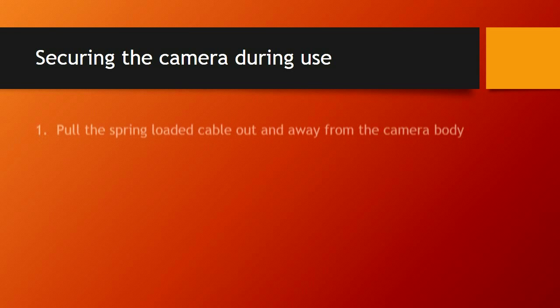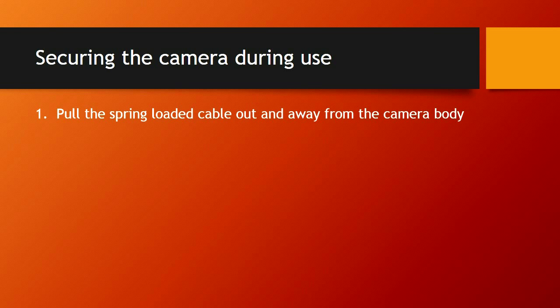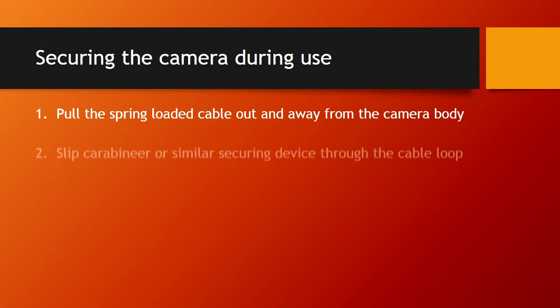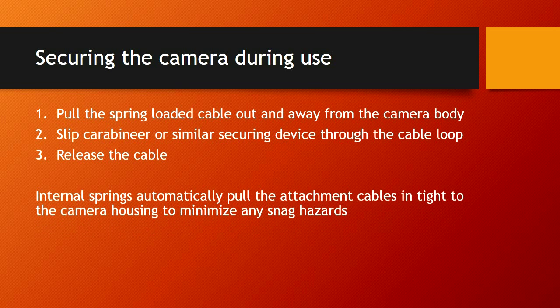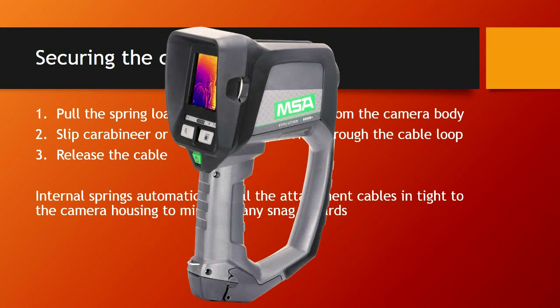Securing the camera during use: pull the spring-loaded cable out away from the camera body — there are 3 of these, one at the base of the camera and one on each side of the display screen. Pull it out, slide the carabiner through, latch it on, and release the cable. The internal springs automatically pull the attachment cables in tight to the camera housing to minimize snags. We recommend hooking to the cable attachments on the side of the screen to carry the camera in a different position and hopefully have less lens damage, since we typically break quite a few lenses from carrying it by the butt of the handle and letting it bang around.